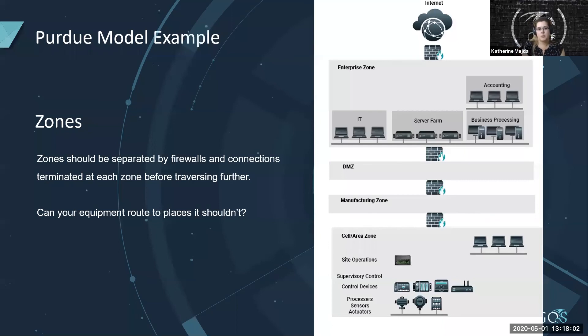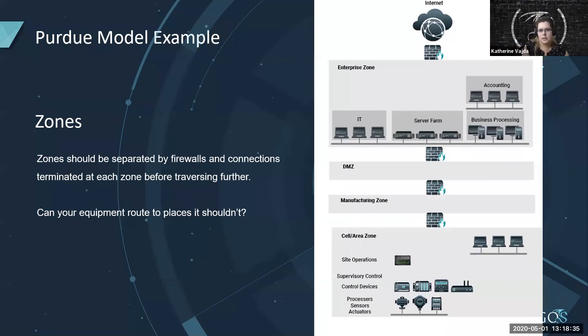Engineering workstations don't need email or internet access either — they could be secured off without that sort of routing capability. One thing to check: can your equipment in ICS route to places it shouldn't? This can be tested by looking at local routes on the device, firewall or router configs, or doing an outbound ping. You can set up a system on the internet that listens on all ports using IP tables, then run a scan for whatever protected device out to that host — did it get through on any ports you didn't think of? You can test this anywhere in your environment; you can put that host in the DMZ. That 40% that require user interaction or internet access to exploit should have no bearing on you if your network restricts that access. If your workstations can reach the internet and also into the process, you might need to reconsider or redesign some of your architecture.